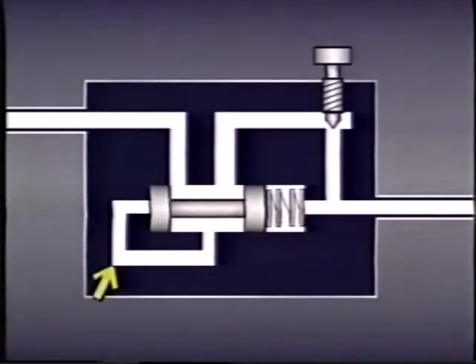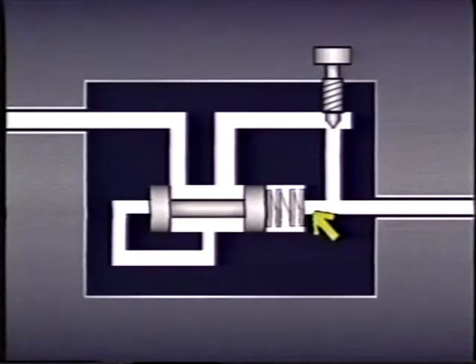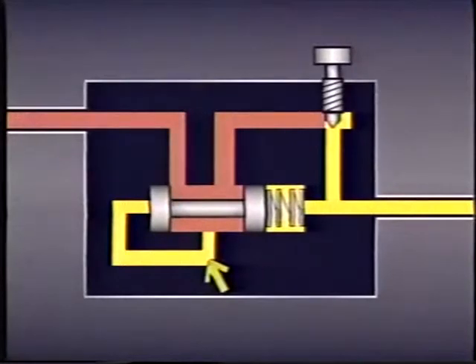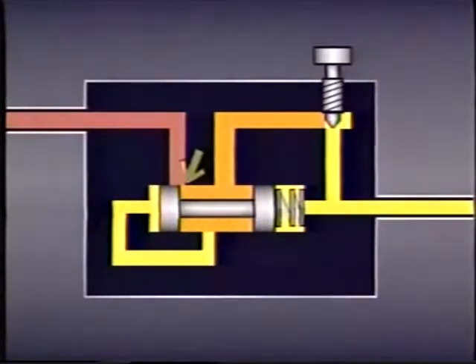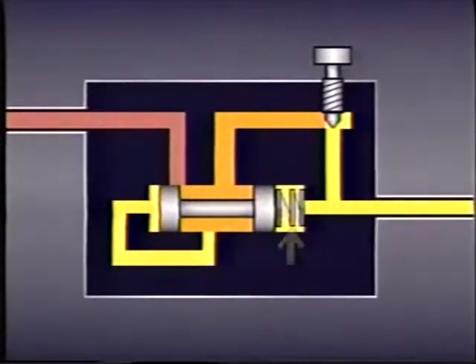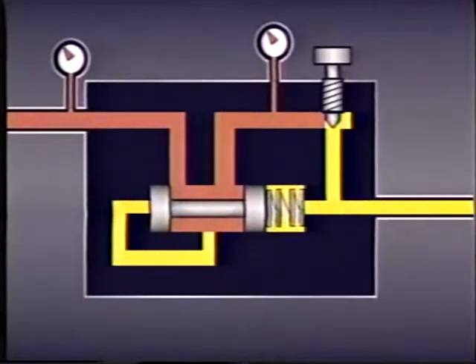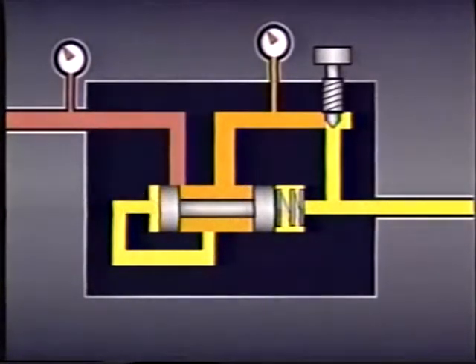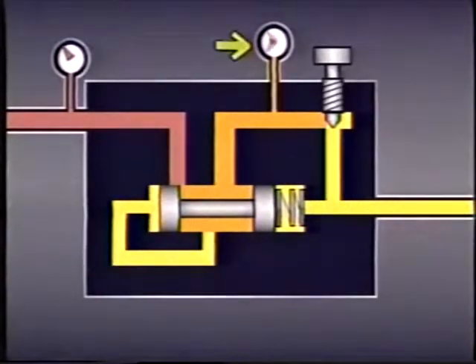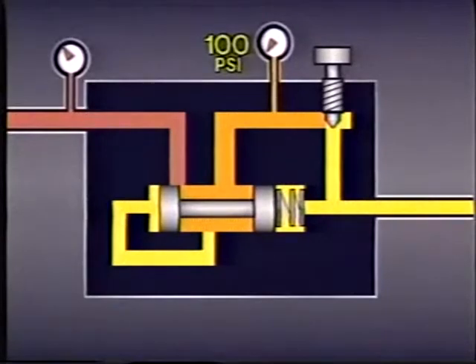One pilot passage compensates for fluctuations in upstream pressure, and the other compensates for fluctuations in downstream pressure. The pilot passage that compensates for upstream fluctuations directs fluid pressure to one end of the compensator spool. As the spool moves, it blocks off part of the flow until pilot pressure equals the tension pressure of the spring. For instance, suppose the valve has a 100 PSI spring and inlet pressure is 500 PSI. In operation, pilot pressure will push the spool over until pressure downstream of the restriction created by the spool is reduced to 100 PSI, the tension pressure of the spring.